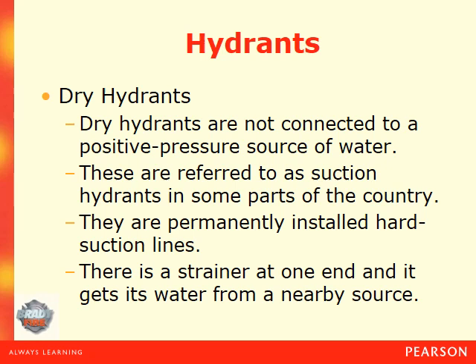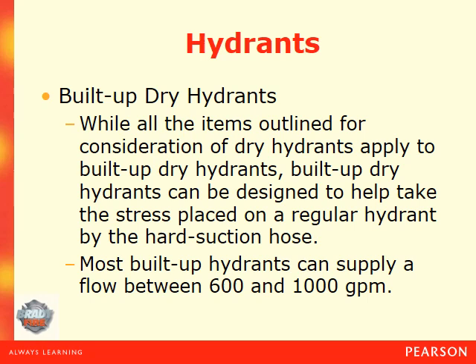Dry hydrants are not connected to a positive pressure water source — they are referred to as suction hydrants. In some parts of the country they are permanently installed hard suction lines with a strainer at one end, drawing water from a nearby source such as a pond, stream, creek, or river. Most built-up dry hydrants can supply a flow between 600 and 1,000 gallons per minute.